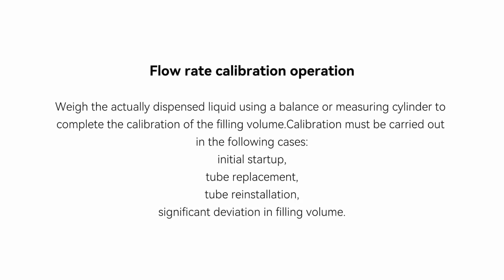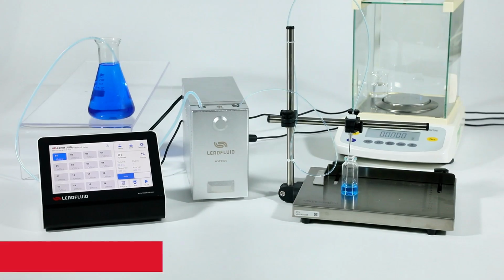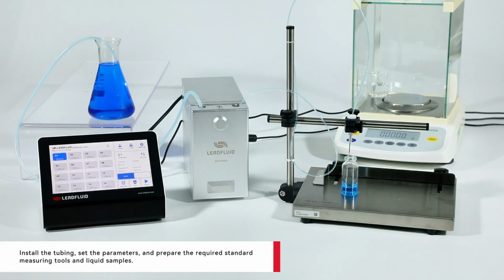Flow rate calibration operation. Weigh the actually dispensed liquid using a balance or measuring cylinder to complete the calibration of the filling volume. Calibration must be carried out in the following cases: initial startup, tube replacement, tube reinstallation, significant deviation in filling volume. Install the tubing, set the parameters, and prepare the required standard measuring tools and liquid samples.